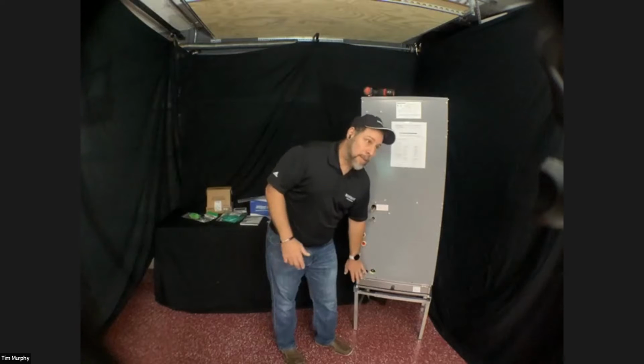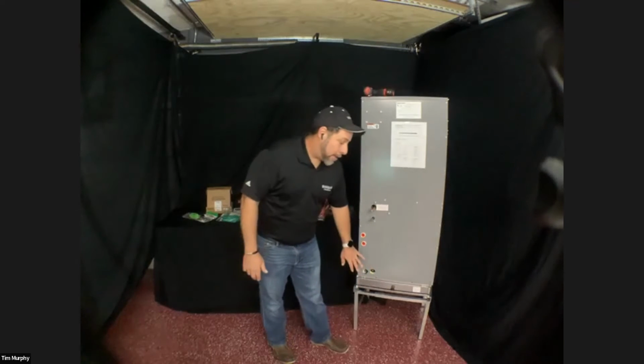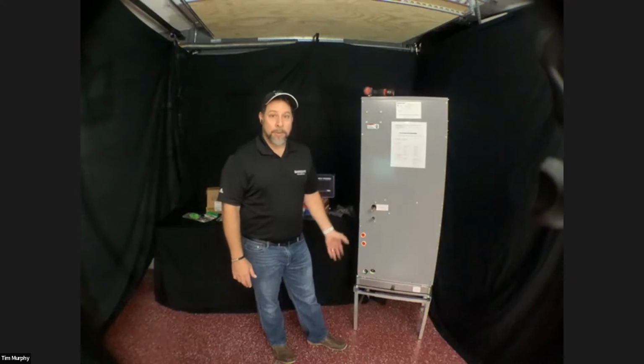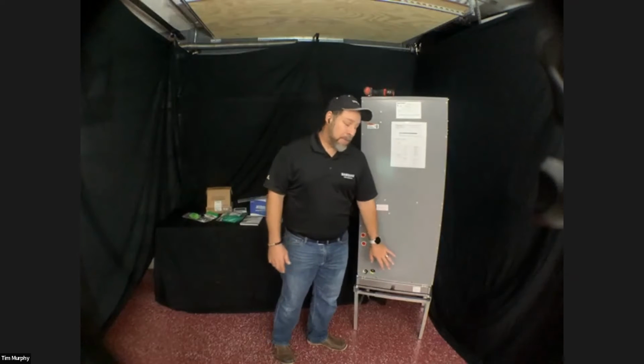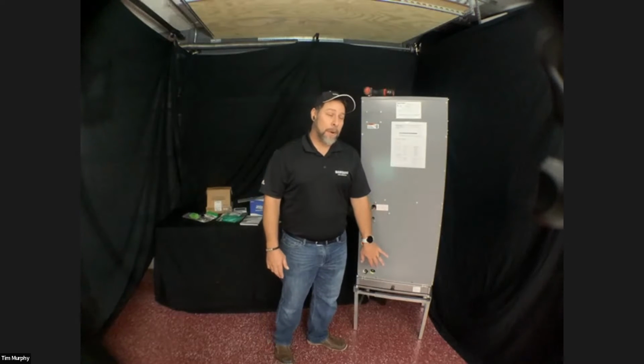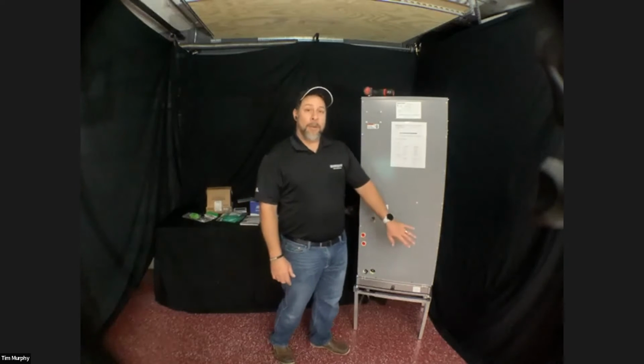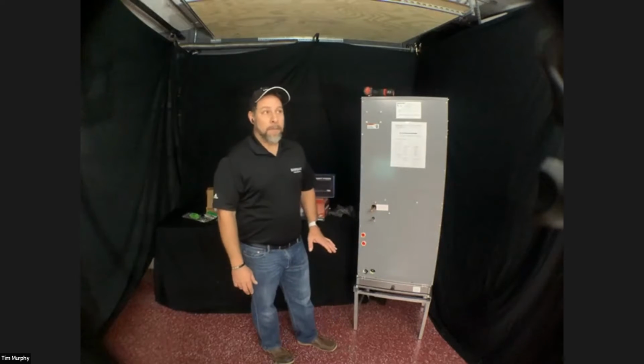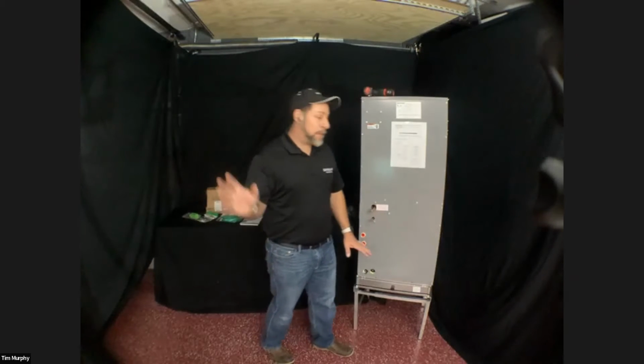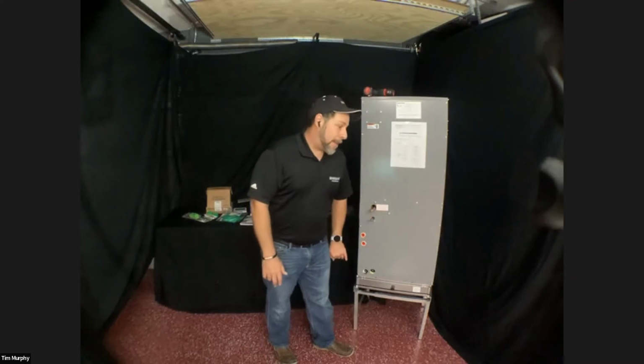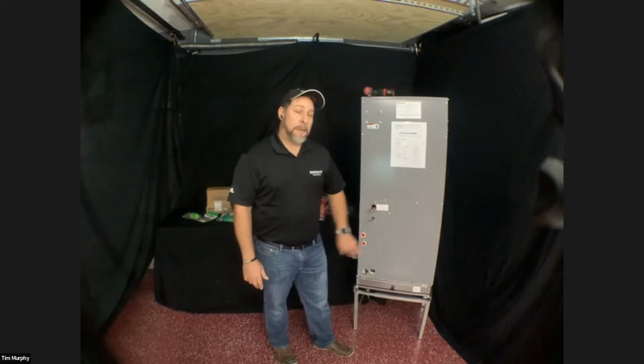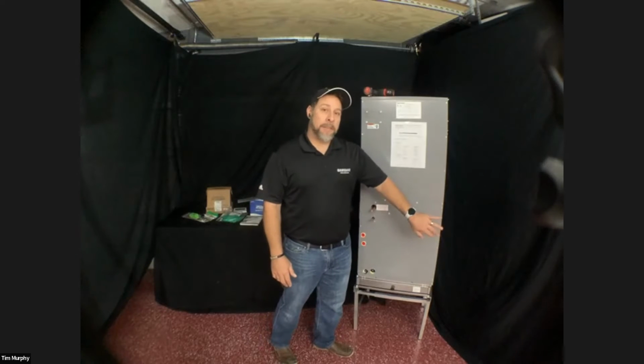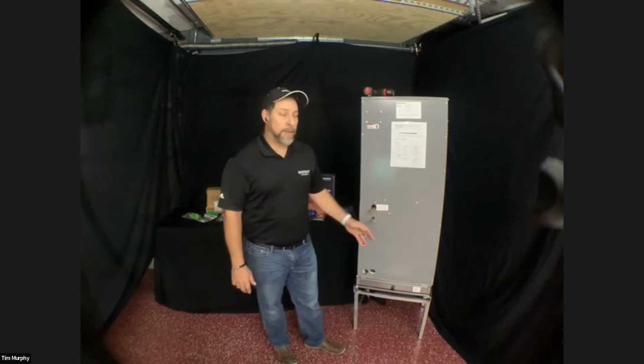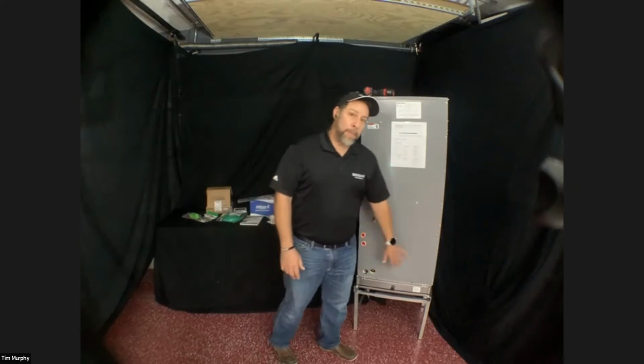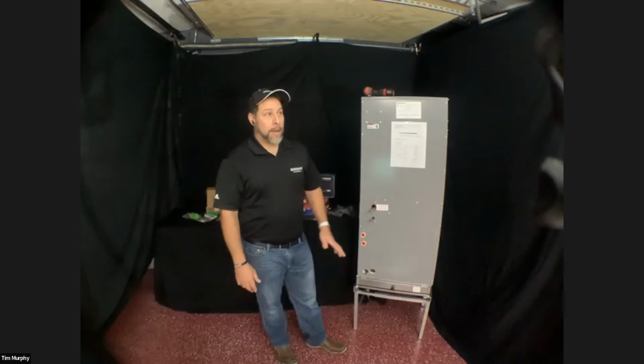And I recommend these. If you're putting these in and you don't know it already, pull those rails out. If you have customers that you've already installed these filter racks on before, you may want to talk to them about going with a 2-inch filter. I went to a job site call the other day, and they had the 1-inch filter on there, and the filter alone gave me a 1/2 inch of static pressure. With the filter in, it was 0.6. Filter out, it was 0.1.